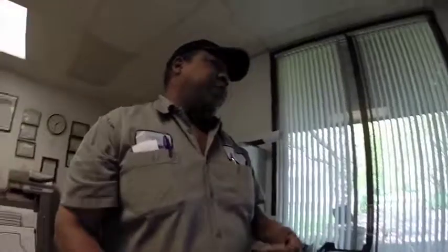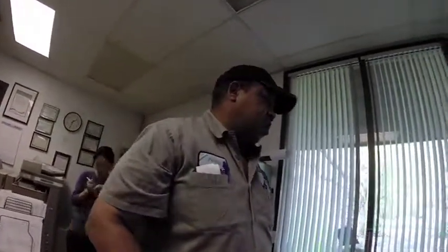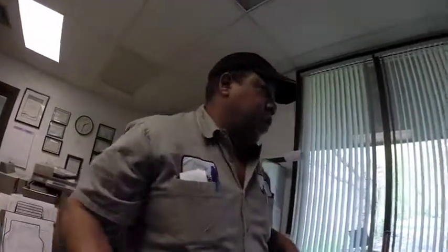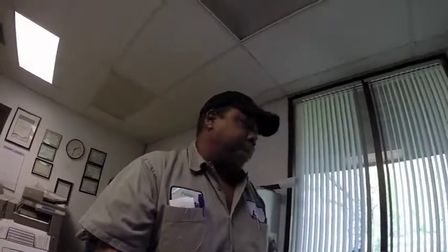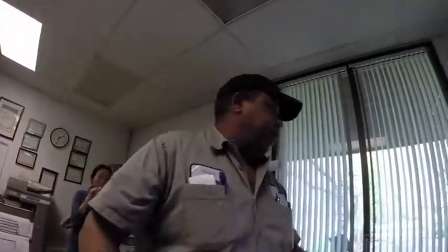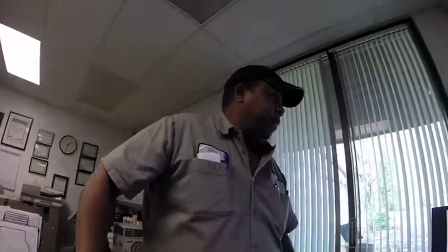And these are turbo blowers, airless blowers. These have been put in for maybe 2 years now. What's the horsepower? I don't know, about 200. They're turning right now at 2,500 RPM. So these things are just spinning really fast. You usually only use one blower? Depends on how much air I need, but for this time of year, yes, just 1. And I'm running on all 4 aeration basins. I'll take it down and show it to you.